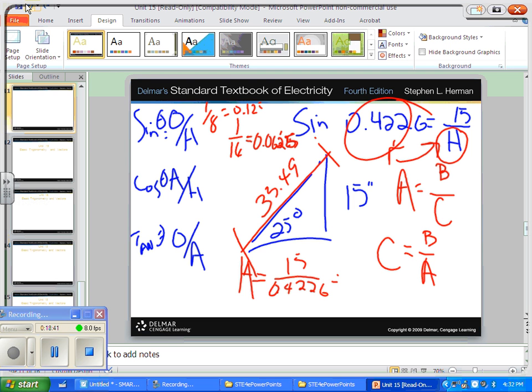So here we are. We found how long between the bends, 33 and almost a half inch. And if we mark it on the pipe, we're going to put our first mark there. We're going to go out 33 and a half, and just before the half mark, we're going to put a pencil mark. Just before, so it lays just inside the half inch. That's going to be close enough. And that's a good example of how to use this stuff.